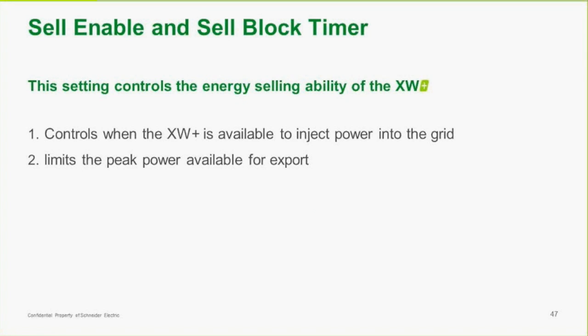Sell enable and Sell block timer, we touched on that before. Sell enable controls when the XW is available and limits the peak power available for export. And the Sell block timer, if you don't want to sell power to the grid and want more self-consumption, you can set up that block timer to do that.